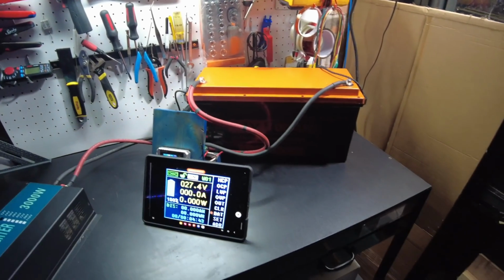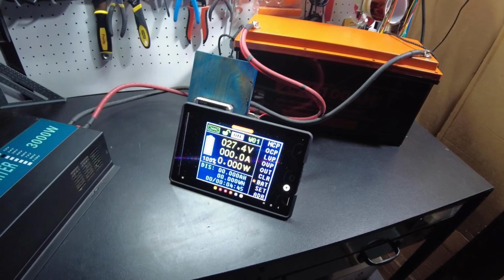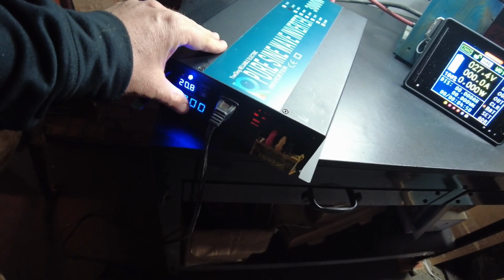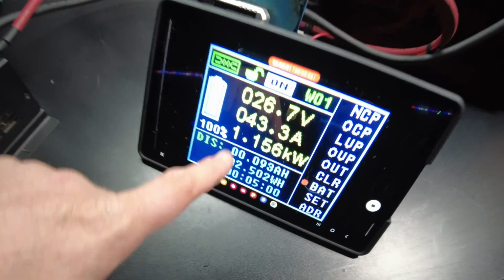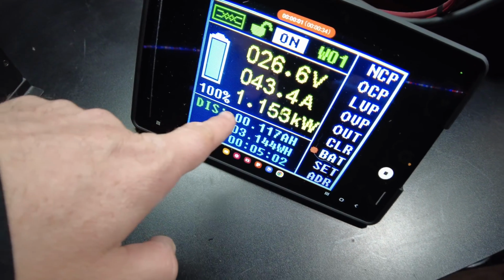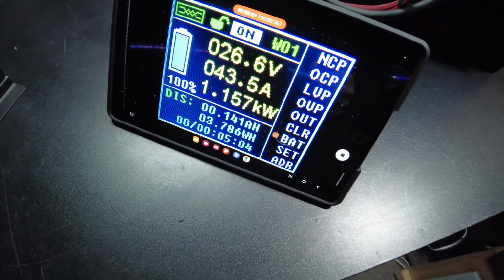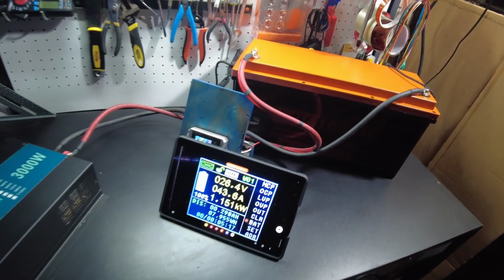All right, the battery is fully charged, and now we're going to do a capacity test. So let's turn on the inverter. There we go. Running the little heater as the load. And we're pulling about 43 amps, 1.15 kilowatts. All right, so we'll just let that run and we'll see what we get.